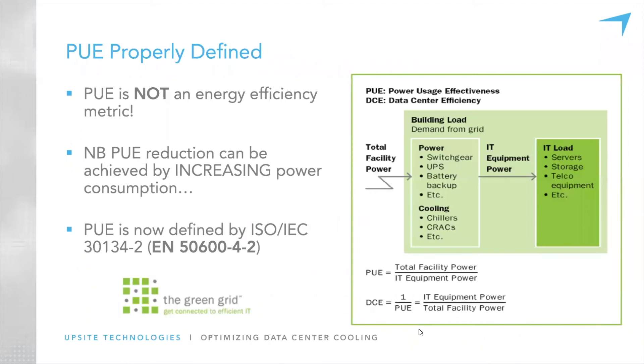To reiterate: PUE is now properly defined as ISO/IEC 30134-2. If you're not using that document, you're not referencing PUE — you're doing something else entirely. An important point is that PUE is not an energy efficiency metric. It never has been and never will be. It does frustrate me continually that people refer to PUE as an energy efficiency metric.